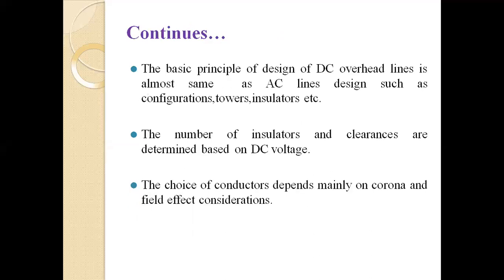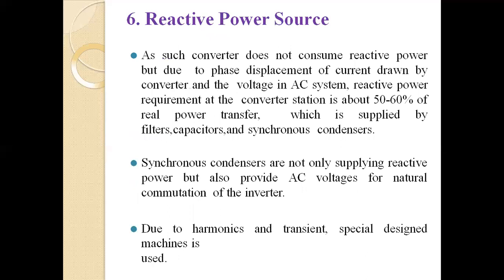The basic principle of design of a DC overhead line is almost the same as AC line design, such as configuration, tower, insulators, etc. The number of insulators and clearances are determined based on the DC voltage. The choice of conductor depends mainly on corona and field effect considerations.